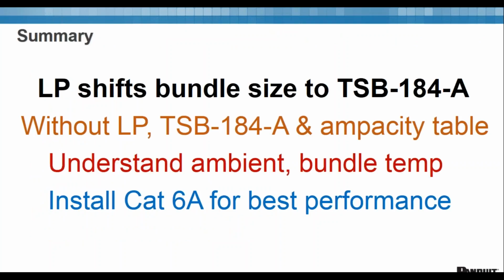So in summary, LP shifts your bundle size restriction to TSB 184A. If you have an LP rated cable, your major concern is going to be performance. Without LP, you need to refer to both TSB 184A and the ampacity table to understand bundle size. You will need to know what your ambient temperature is and how hot your bundles get. And if you can see anything through all these examples, Category 6A does have the best performance. So that really ends this portion of the presentation.